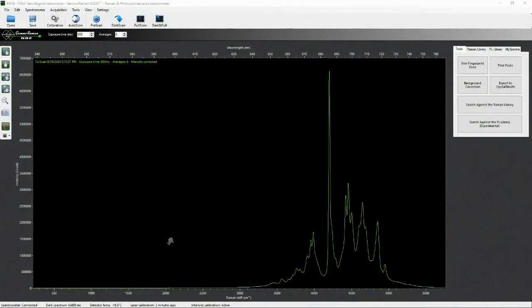While Raman peaks are measured in cm-1 on a relative scale having the wavelength of the laser, in our case 532 nanometers, as a zero value, PL peaks are always referred to an absolute scale expressed in nanometers. Since the software will feature both spectra on the same screen, for practical reasons the Raman scale is displayed at the bottom, while the nanometer scale where to read the PL peaks values is on top.